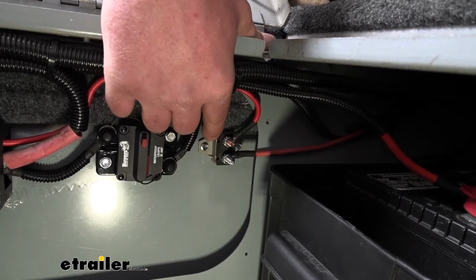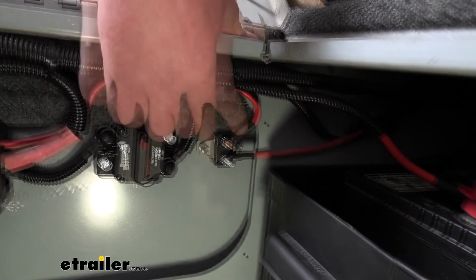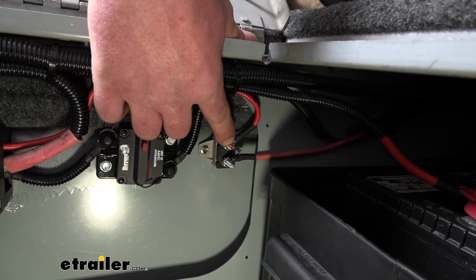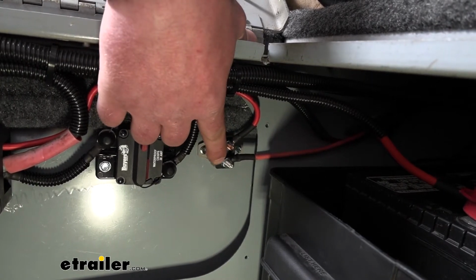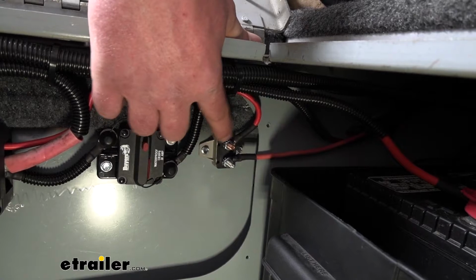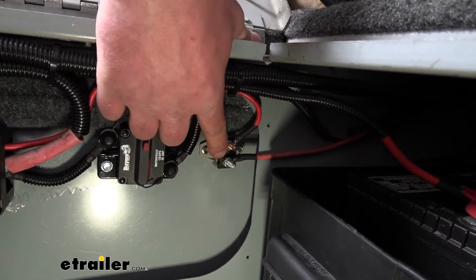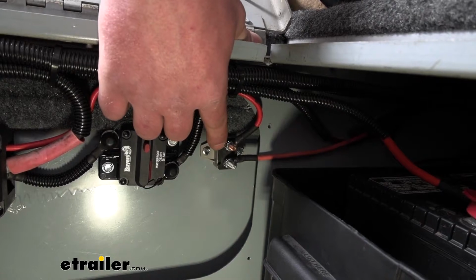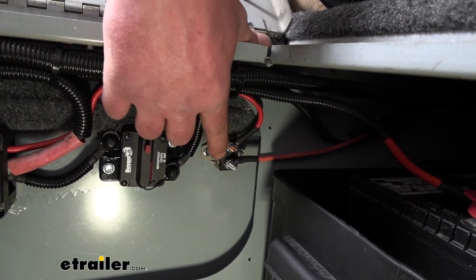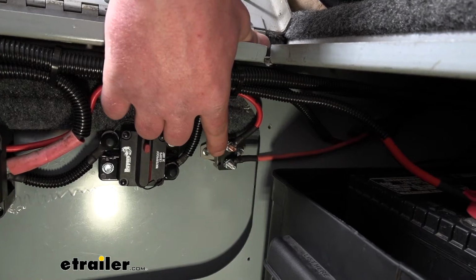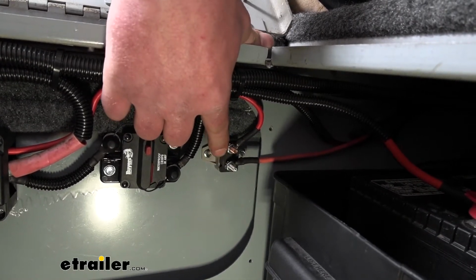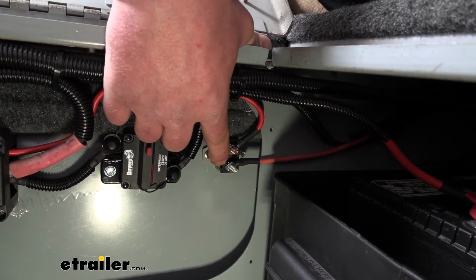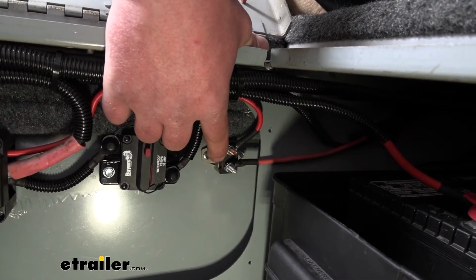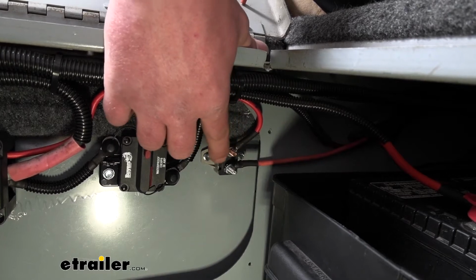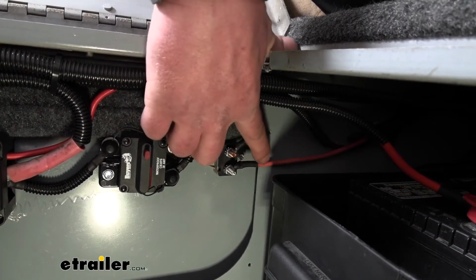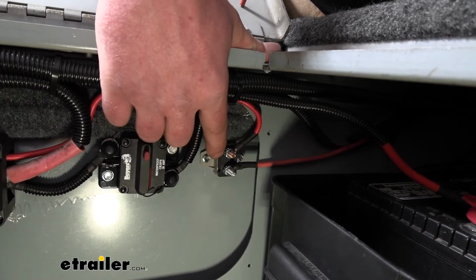More or less, the way a circuit breaker works is really simple. Current is going to come from your battery, go across a contact to this stud, and out to your accessory. There's a contact that connects these two together, and whenever energy goes across that contact, it's going to create heat. If there's too much heat drawn from a short or an electrical issue, that contact is going to break and disconnect the circuit, so battery power can no longer go to the other side and out to your accessory. That's what keeps it protected.